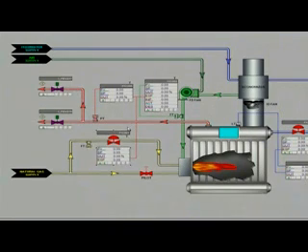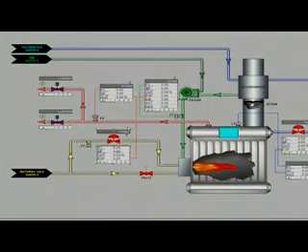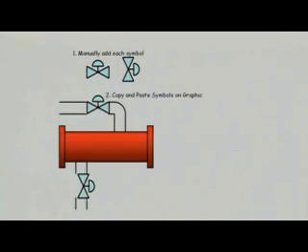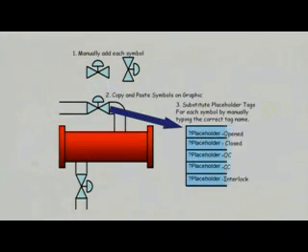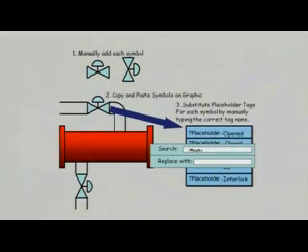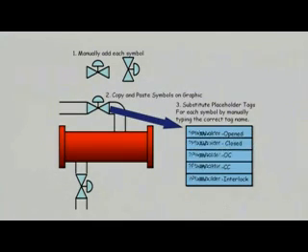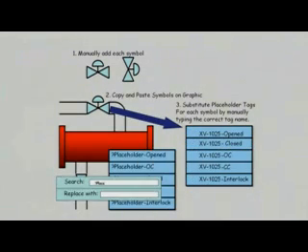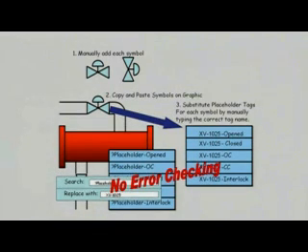With Wonderware, you must manually add each symbol to the appropriate graphic, then using substitute tags, link the symbol to the appropriate tags in the tag database by manually typing the correct tag name. There is no error checking to make sure that the tag being assigned actually exists in the database. Pretty time-consuming.